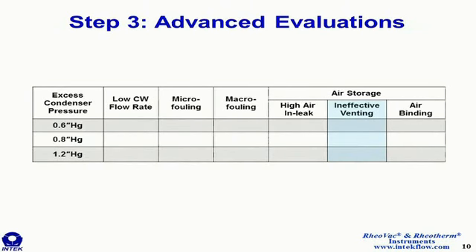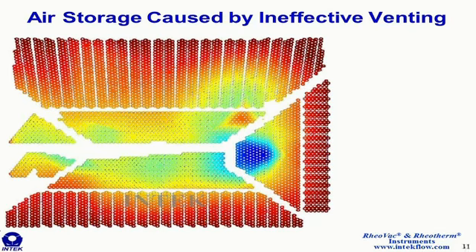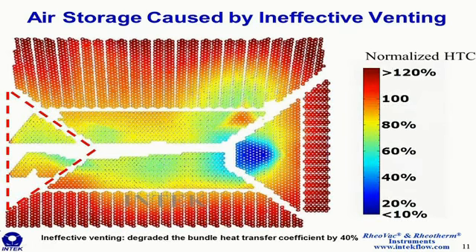The next case study that I have is air storage as a result of ineffective venting. So again, this is when air in-leakage stays the same, but the vacuum equipment capacity decreases for one reason or another. This is an Ingersoll Rand bundle. Again, this is a 320 megawatt unit showing 1 of 4 bundles. And those 4 bundles are split into 2 different shells. Here's the performance profile. You can see the air cooler zone over on the left there. That's where the air offtakes are connected to the left-hand side there. You can actually see an air-bound zone that has already formed. Notice it is far removed from the air cooler zone.